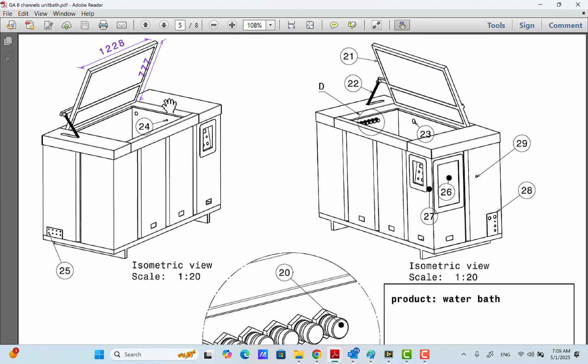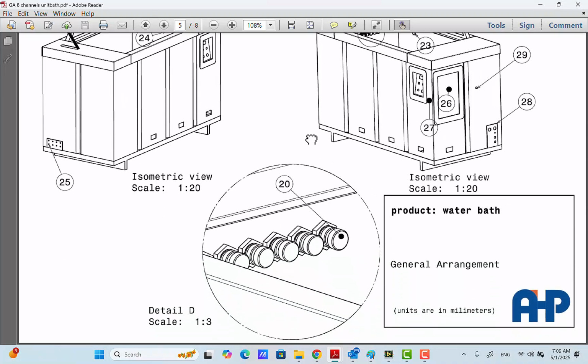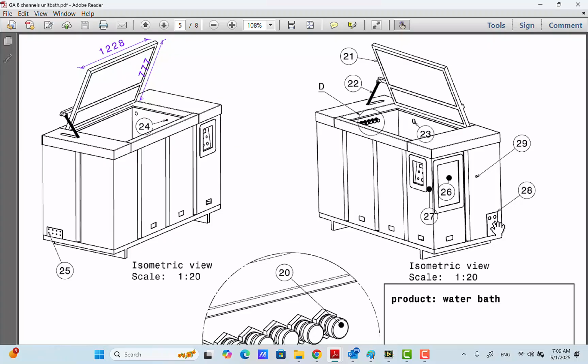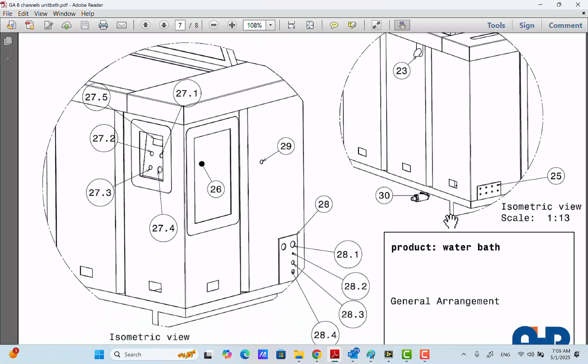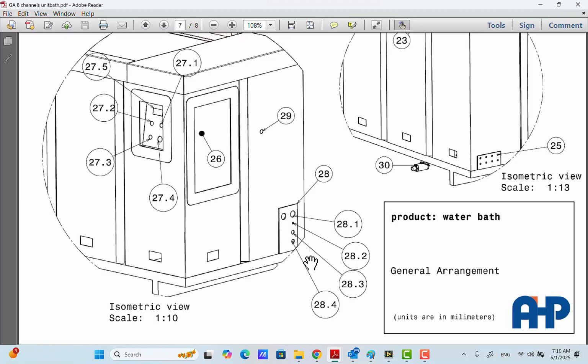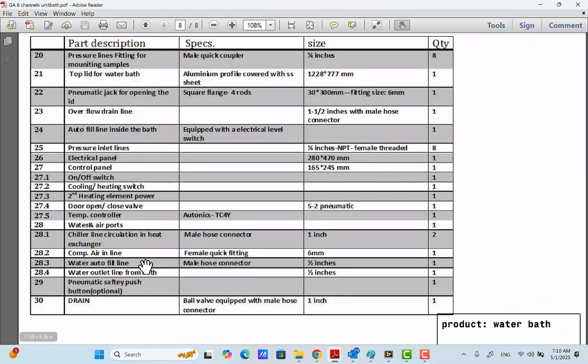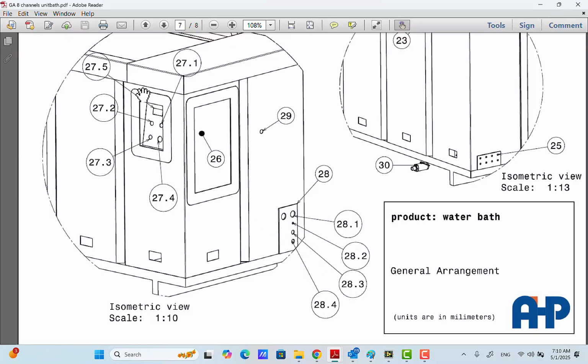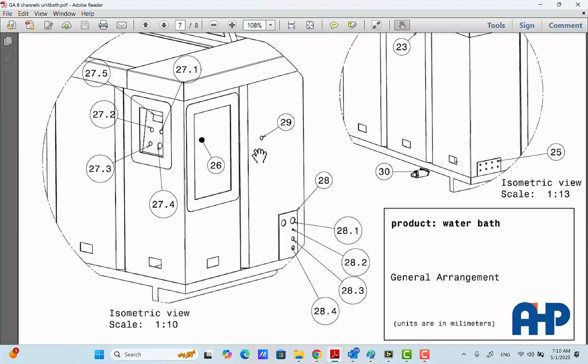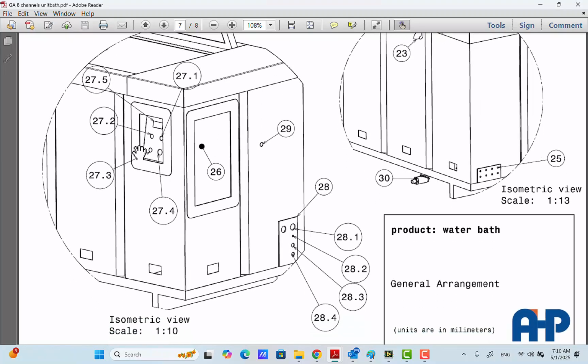When you receive the tank, don't forget to fill it with deionized, tapped, clean water, soft water. First of all, fill it from the top, and in the next stage, connect the autofill line here. You have the autofill line here. You see in this model, on the right side there are connections for the autofill. I mean 28.3 here. Yes, water autofill line. This one is the autofill line. Whenever the water level inside the tank goes down because of evaporation and anything, the level switch will open the solenoid valve to fill the water into the tank to keep the water level inside the tank.